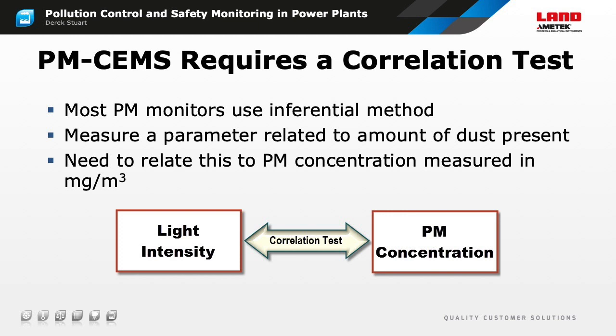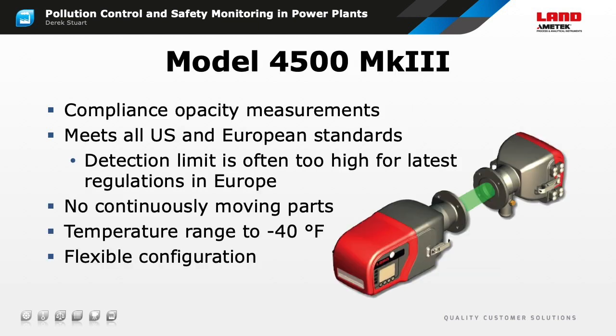The drawback of the correlation test is that it's rather time-consuming and expensive, since it generally requires several days of work by a skilled stack test team. The AMETEK Land 4500 Mark III is an opacity monitor which meets the requirements of European and North American compliance rules. It has QAL1 approval in Europe, and each instrument comes with a certificate of conformity showing compliance to ASTM D6216 as required by the US EPA Performance Specification 1.